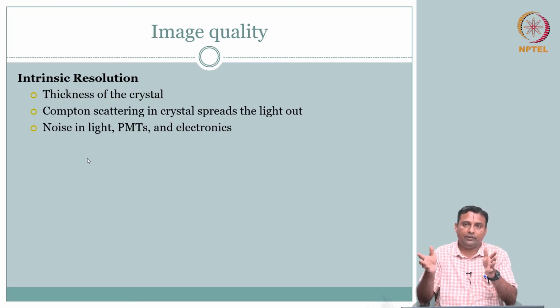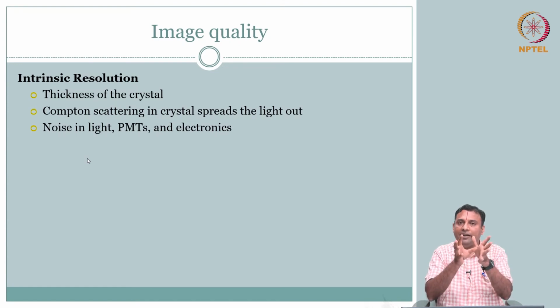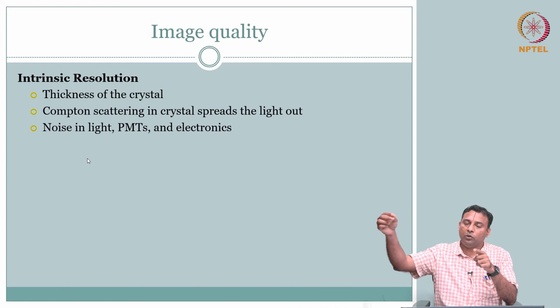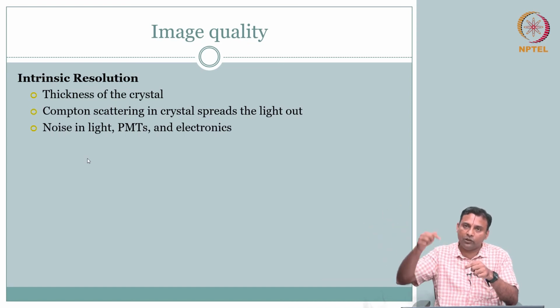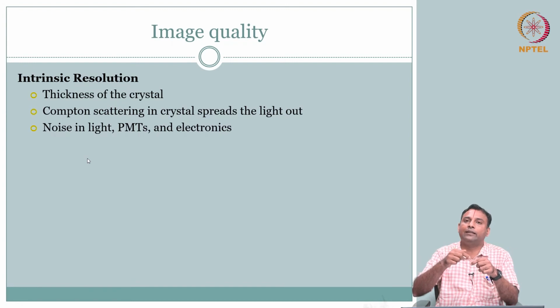That is it. We could not recover from that. Okay, it was directly the point spread of the intensifying screen that had an effect. Whereas here, the point spread, similar to there, is not directly recorded. The point spread goes and hits probably multiple photomultiplier tubes. So you get the raw signal out, and then you use all this signal to calculate the x comma y.